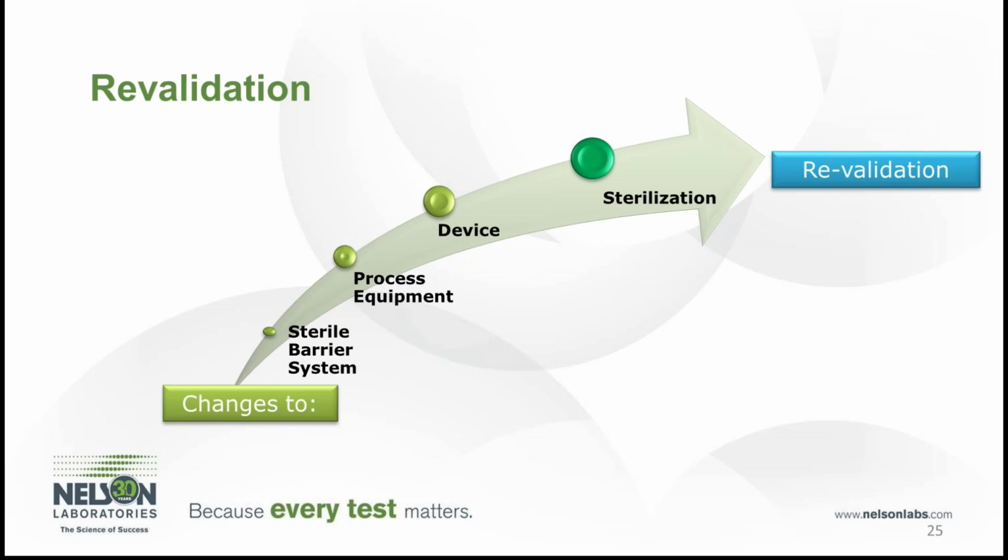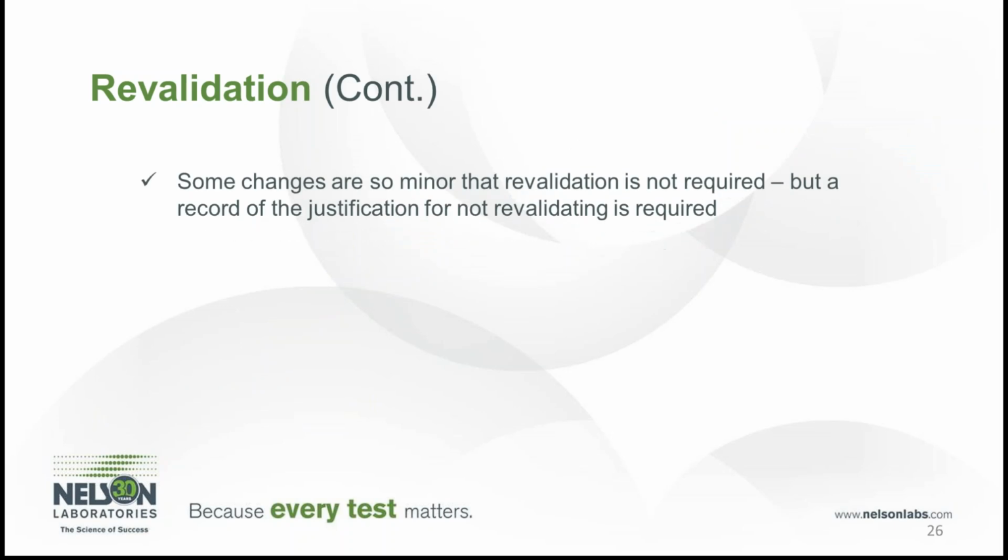This is one reason why we recommend running your package validation after the sterilization validation is complete, so that you make sure that the sterilization you're using has been validated. End user complaints or negative trends in quality, or maybe changing of the transportation system, going from a local delivery process to a larger scope. You're used to sending out one box of 10 units and now you're changing it to sending out a pallet. All those things can cause a revalidation to be necessary.